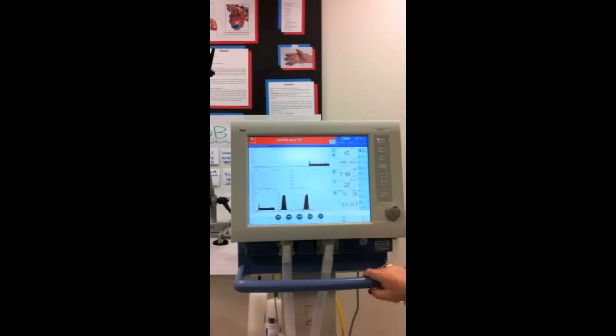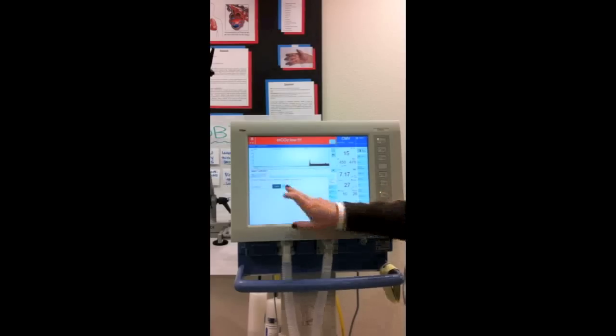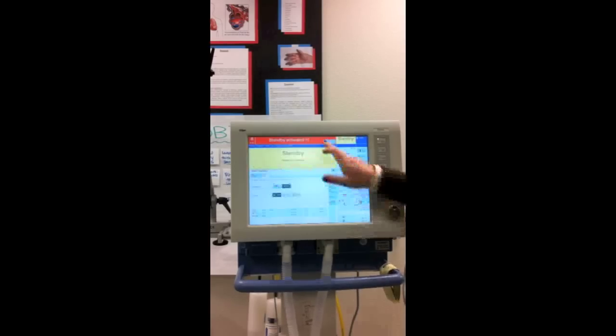Are there any questions? So for the pre-use check or calibration, it requires specifically a test lung? This one does, yes. And this one's called the device check. So for the midterm we would have to get the test lungs out? Yes, have it out. Okay. Yep. So remember, standby: push the button, hit standby, confirm, then alarm reset and confirm again to actually get it into standby.